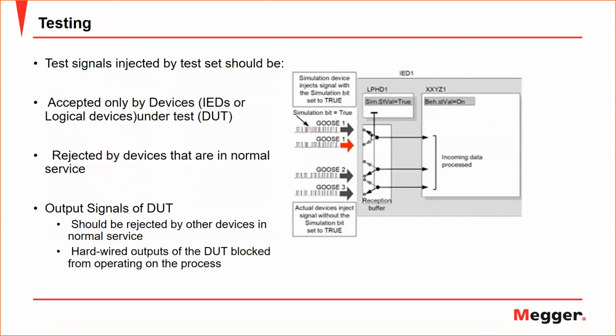That's why test signals should always be injected with simulation flags, especially in a live environment. And thus, devices should only accept these under test mode as well. Since once you start connecting and start publishing, even if you are not injecting anything or putting any value, everybody in the network will see this. So you need to make sure that everything other than the device you want to test is in test mode, and also maybe the hardwired outputs are blocked or using test/blocked mode from operating the process in case you are in a hybrid environment.